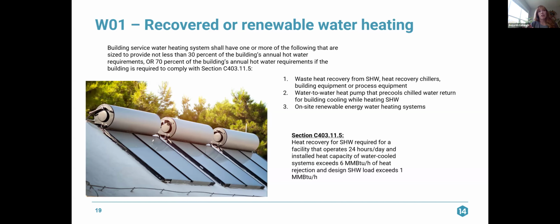But then they also have a very large heat rejection, and they have water cooled chillers that are providing that heat rejection. That building is going to be required to provide heat recovery for that service hot water. So we're talking about utilizing the heat recovery from the chillers to preheat the domestic hot water. If you are that building and you want to achieve credits under W01, you have to provide 70% of the building's annual hot water requirements to achieve credits under this.